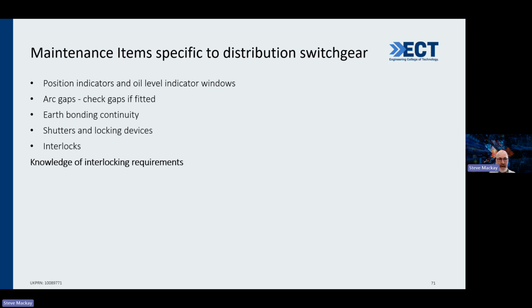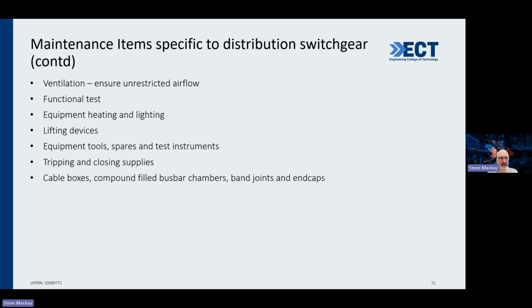No war stories on low level of oil? I can probably give a few on some remote sites which have sort of been forgotten. They never operate much, and then all of a sudden you discover no one's been maintaining it for the last 10 years. Arc gaps, obviously check gaps. Earth bonding continuity. Shutters and locking devices, interlocks, obviously have a knowledge of the interlocking requirements.